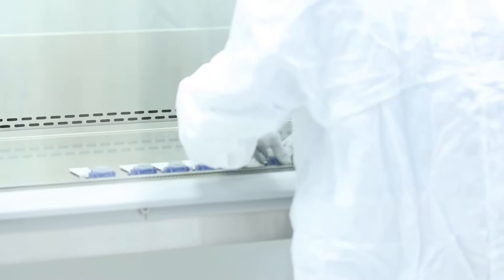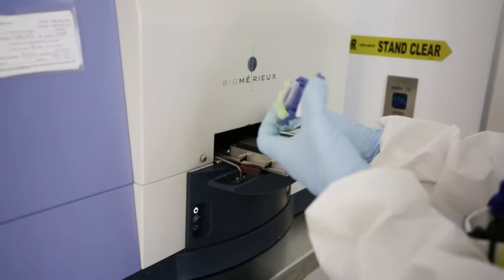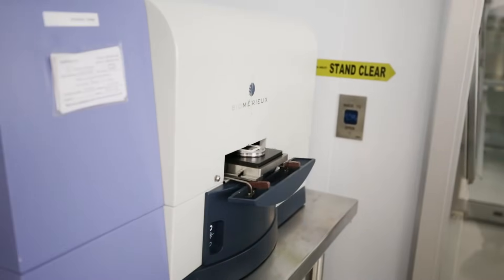This fluorochrome is important because it allows structural integrity of the cell to remain. When a sample is placed into the machine, the membrane is scanned by a laser looking for the expressed fluorochrome. This allows the microbiologist to then visually confirm possible microbial contamination.